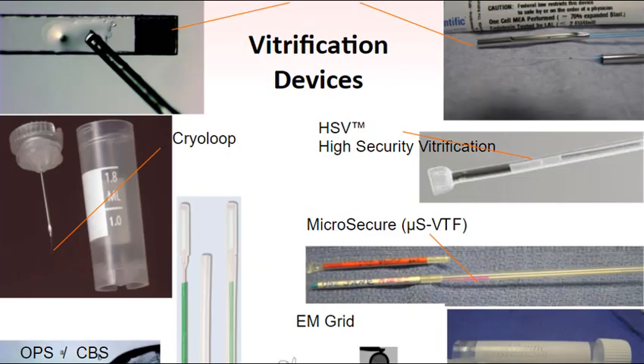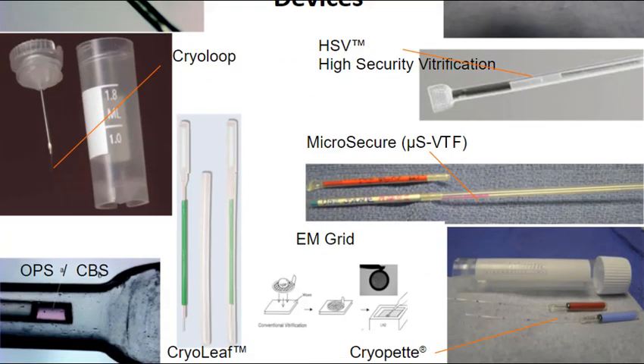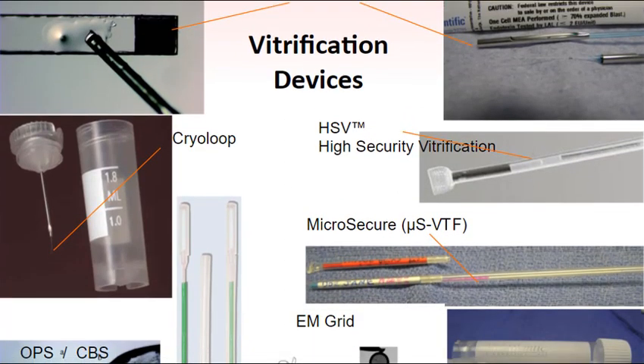Over 25 different vitrification device systems have been developed for the experimental or clinical vitrification of embryos. Shown here are commercialized and non-commercial systems used in Clinical Assisted Reproductive Technology, including open and closed systems as well as aseptic closed systems. The latter are double container systems that prevent the actual vitrification device from coming into direct contact with liquid nitrogen, thus preventing any possible cross-contamination in storage.